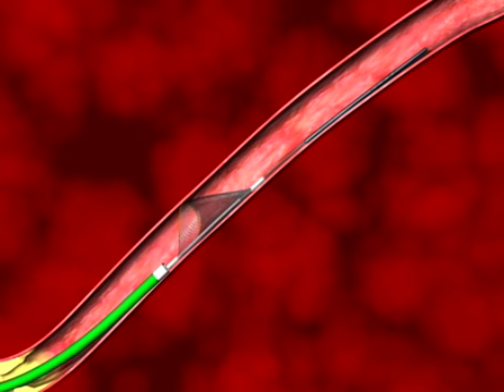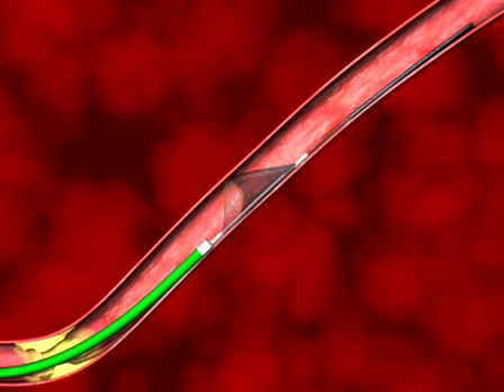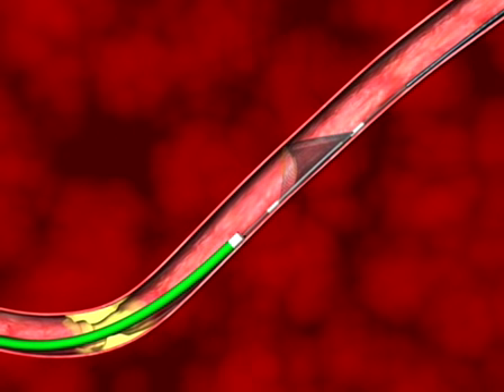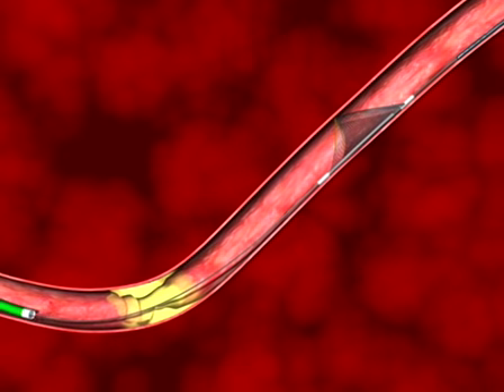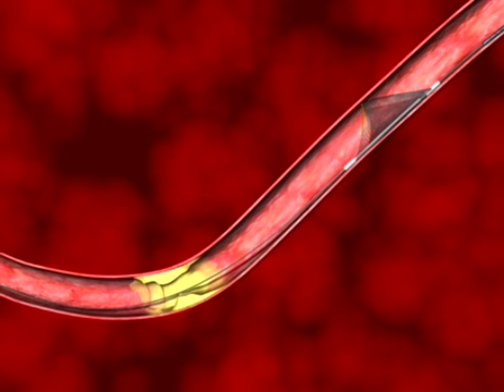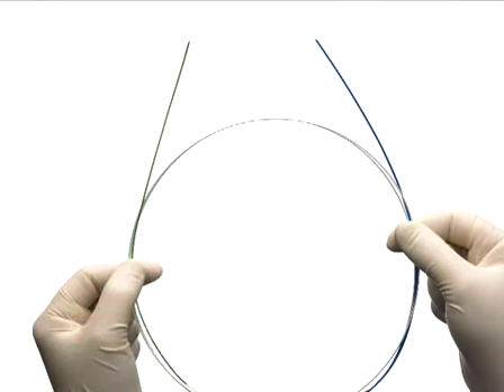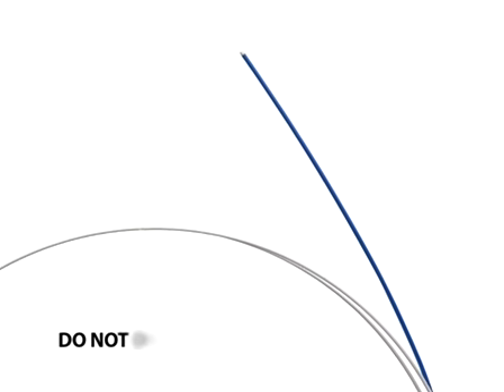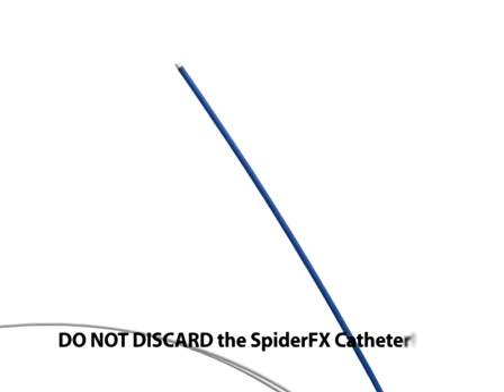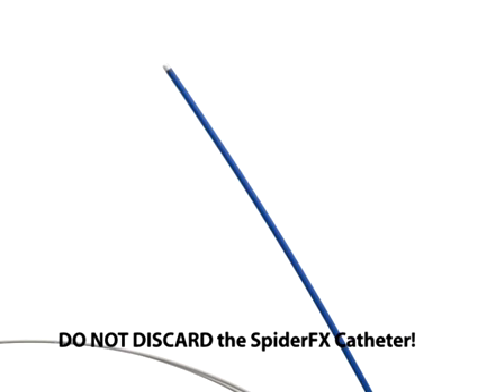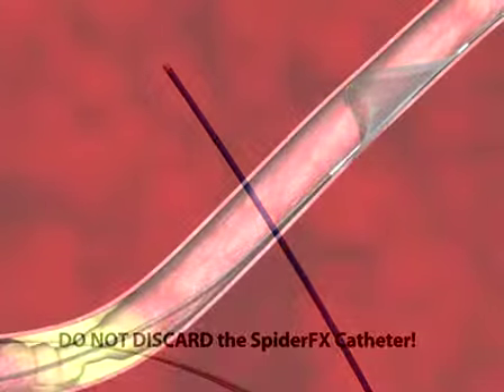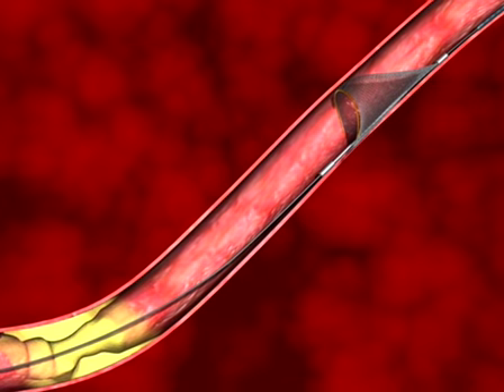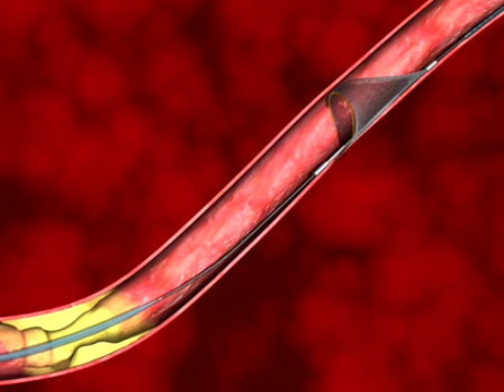Once the filter is deployed and position is confirmed, stabilize the capture wire and remove the Spider FX catheter by gently pulling the catheter proximally. The blue end of the catheter is used for recovering the Spider FX filter. Do not discard this catheter. Proceed with the intervention, using the Spider FX capture wire as the device wire.